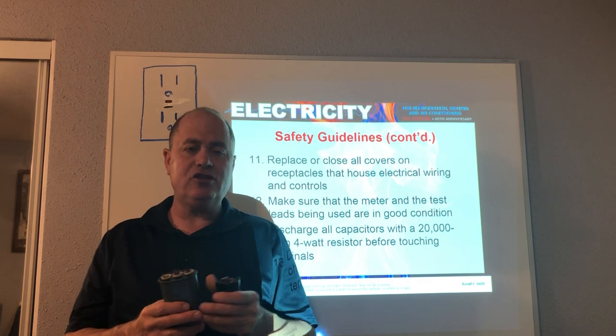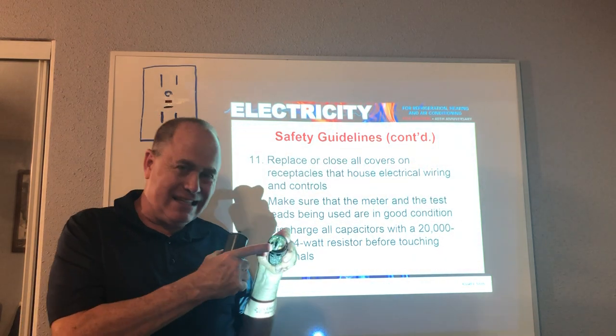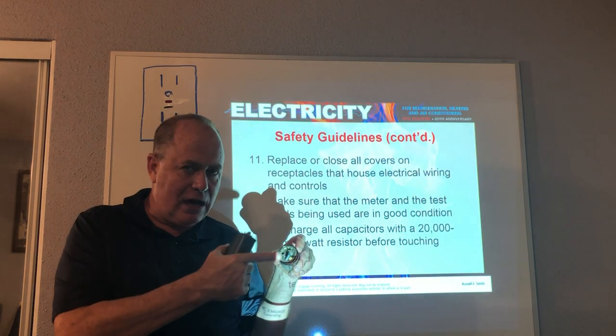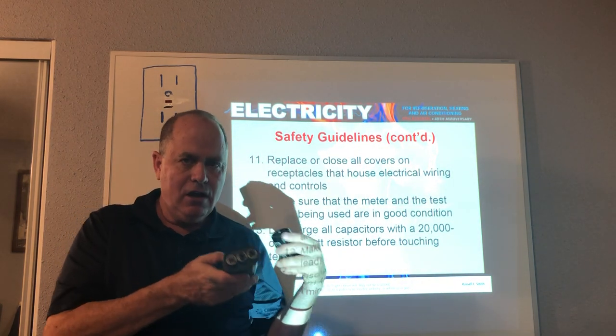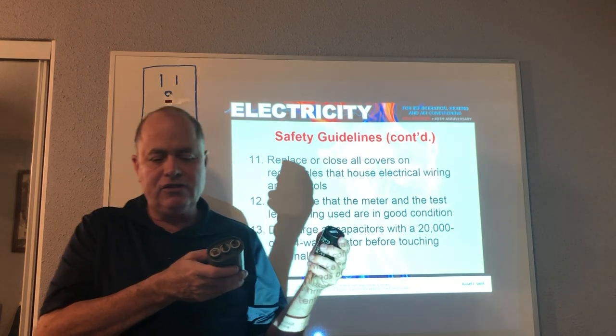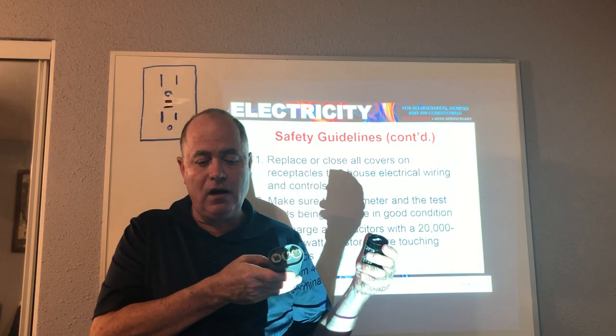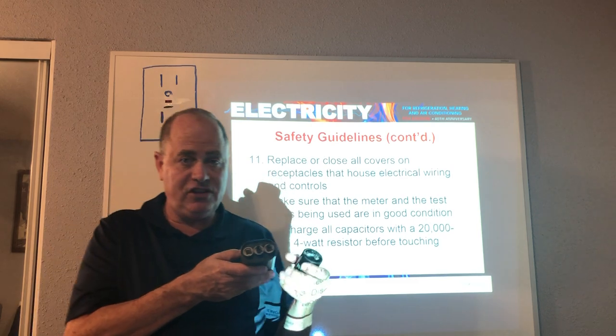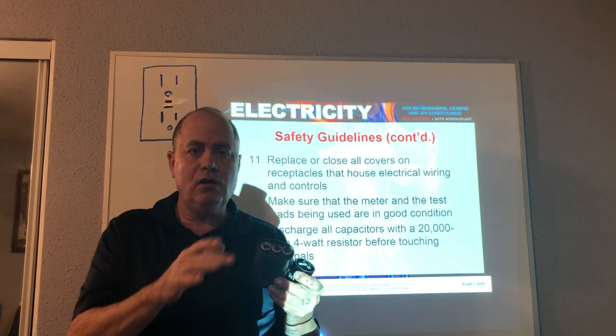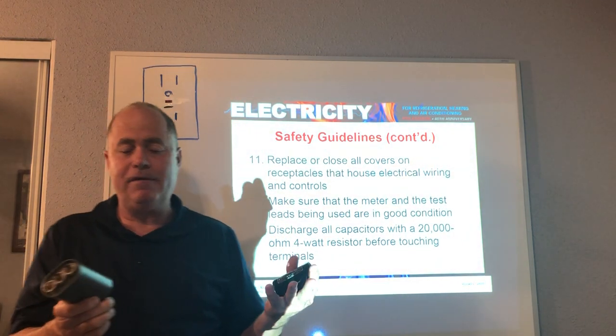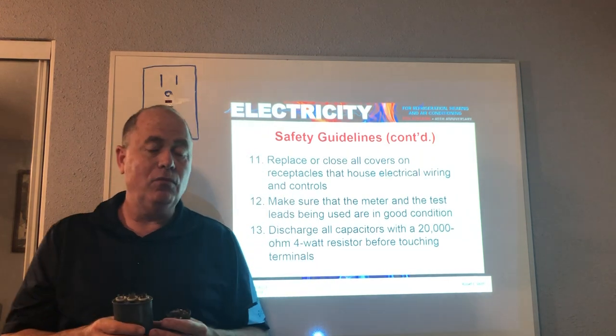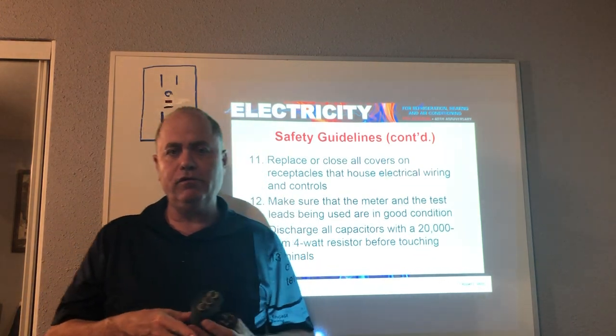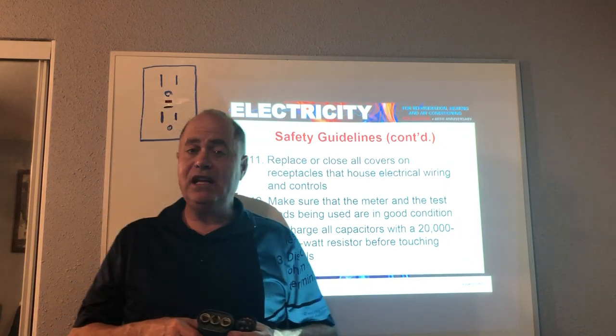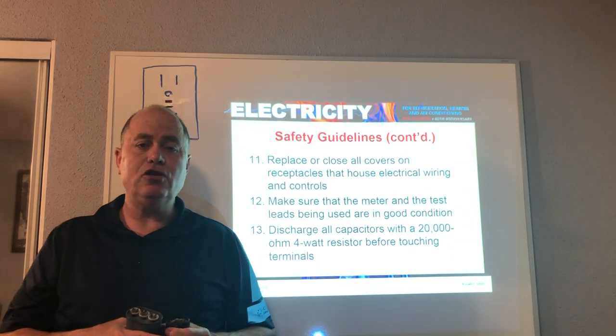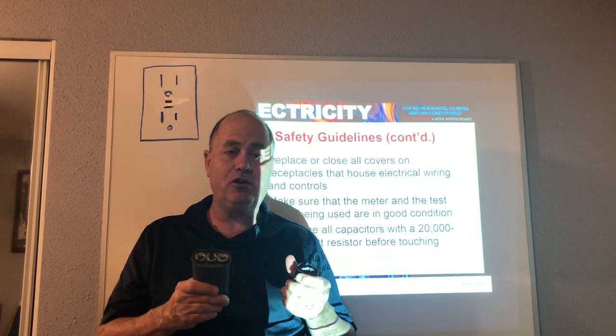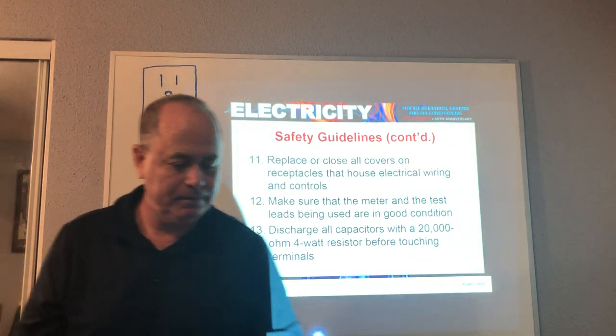So we want to discharge the capacitors. This start capacitor has a built-in bleed resistor that allows the electrons to equalize over time. The run capacitor doesn't, so it's recommended to use a 20,000 ohm, 4-watt resistor, or something similar, to allow the electrons to equalize. If the unit's been off for an hour or so, it's not really an issue, but anything less than that, you could get shocked, so we want to be careful of capacitors even when the power is off.